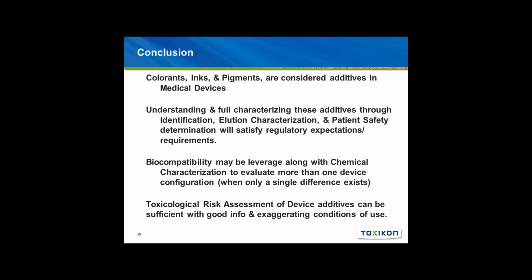So in conclusion, I just want to say that colorants, inks, and pigments are considered additives to medical devices, not just food coloring. And understanding the full characterization of these additives through identification, elution characterization, and patient safety determination will eventually satisfy the regulatory expectations and requirements. Biocompatibility may be leveraged along with chemical characterization to evaluate more than one device configuration when only a single difference exists. And that's our example of the same device that comes in 3 different colors. And the toxicological risk assessment of device additives can be sufficient with good information and exaggerated conditions of use.